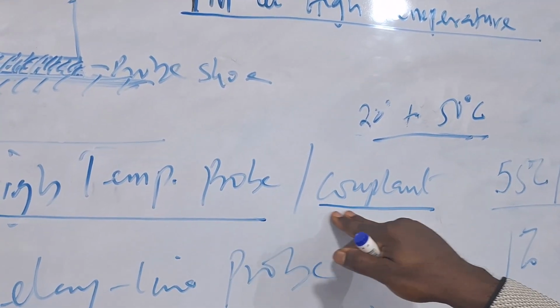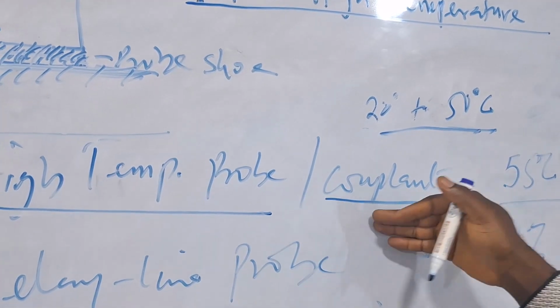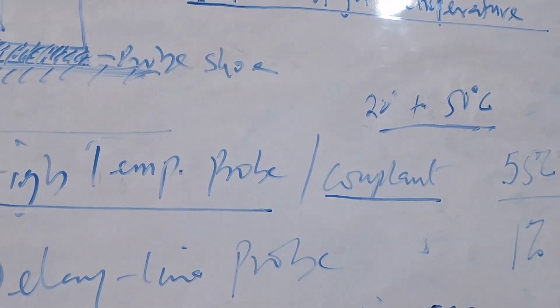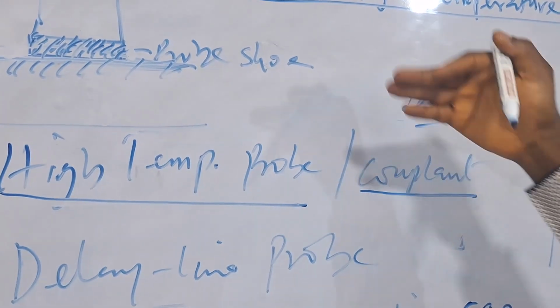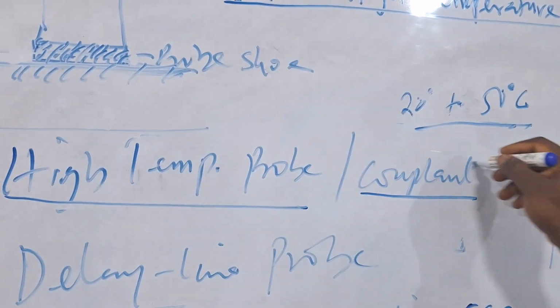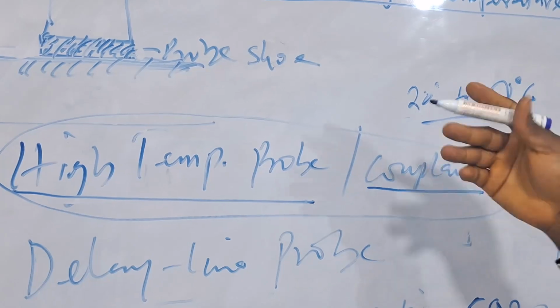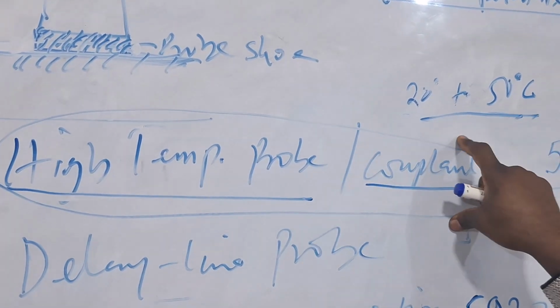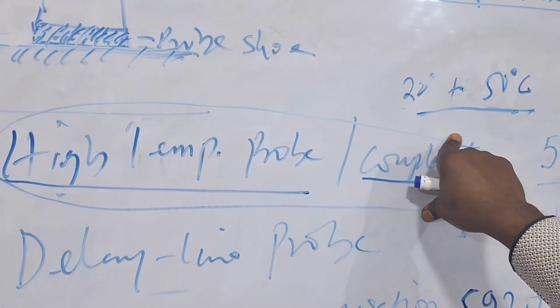In some cases, the high temperature will affect the coupling effect. So to compensate for this, you use high temperature couplant, which does not easily evaporate. In this case, you are trying to, should I say, mechanically compensate for the temperature change.